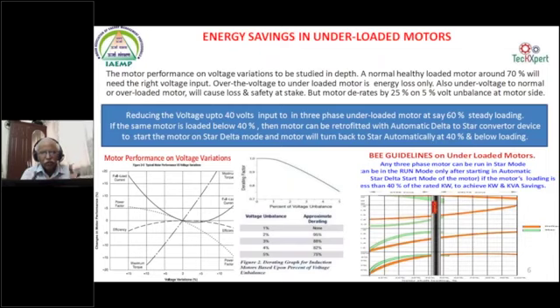The Bureau of Energy Efficiency gives guidelines: you simply retrofit an automatic delta to star converter. Thanks to the electronics, a lot of innovations are happening in electronics that have to come to the industry. It is an EEPROM based controller, an automatic delta to star controller. Once retrofitted, it costs just around 10,000, and it is fitted on the motor panel for loads of less than 30% or 40%.